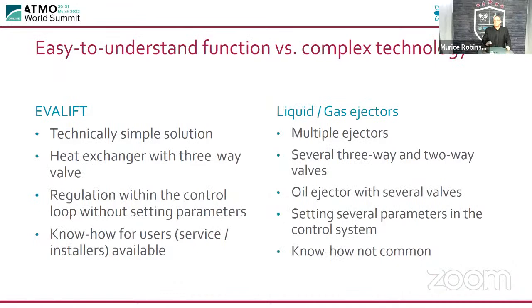The functions are easy to understand, versus complex technology. So EVALIFT is a technically simple solution. This is what I'm trying to get across, that it's really, really simple. With liquid or gas ejectors, you have multiple packs of ejectors, especially when you start going into the industrial field. When it's a smaller installation, it's a lot simpler because there might be 1 ejector or 2 ejectors or 1 bank of ejectors. With EVALIFT, there's a heat exchanger with a 3-way valve, but with liquid and gas ejectors, there are several 3-way valves and 2-way valves. The regulation for EVALIFT is a control loop without setting parameters. With the ejector, there are quite a lot of parameters that need to be set in, and sometimes it's a little bit confusing for the mechanics. But the know-how for users is very, very simple. And with liquid or gas ejectors, you need to have a little bit more training.